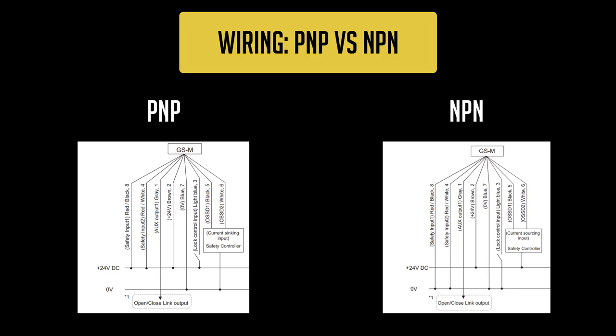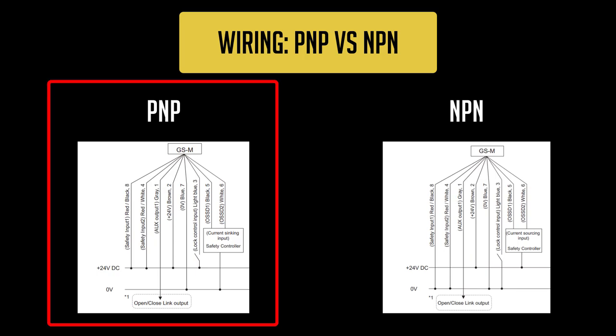Next, we'll discuss the wiring of the GS-M series. For this video, I'll be focusing on the PNP models, which will use 24 volts DC for inputs and outputs. If you have the NPN model, refer to the manual for specific direction, but generally you just need to flip the voltage to 0 volts DC on inputs and outputs for the information to still be applicable.